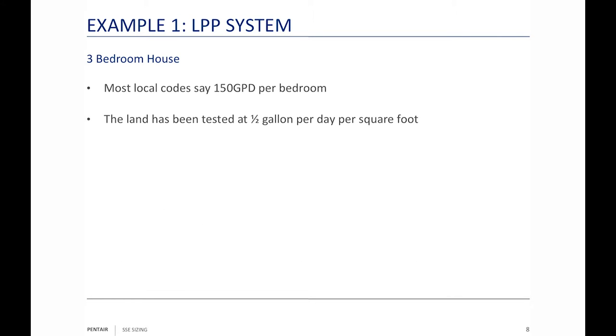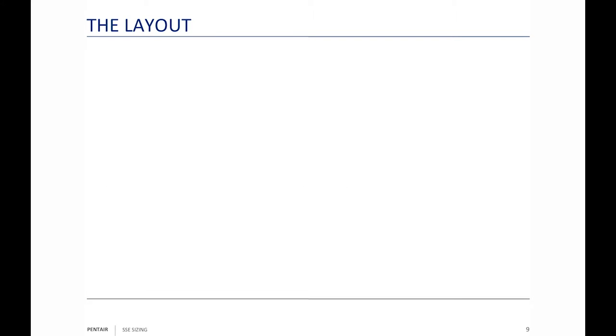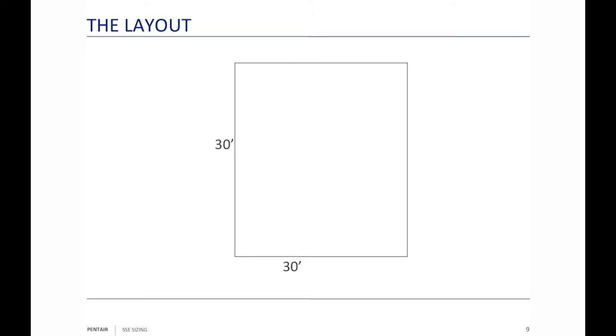The land has been tested at one-half gallon per day per square foot, so we can put half a gallon of effluent water per day per square foot into this leach field. At 150 gallons per day per bedroom with three bedrooms, that's 450 gallons per day we need to eliminate. 450 gallons per day divided by 0.5 gallon per square foot means our leach field has to be a minimum of 900 square feet.